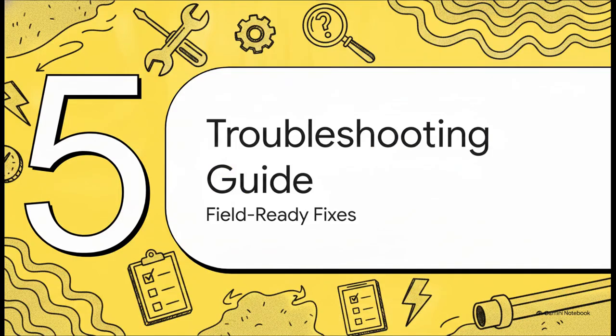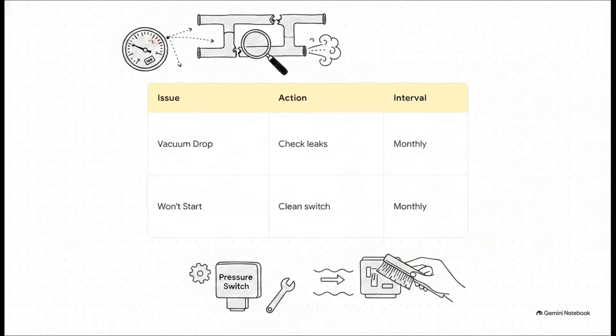All right, Section 5, Troubleshooting Guide, Field-Ready Fixes. Look, even with perfect maintenance, things happen in the field. If you notice your vacuum gauge is steadily dropping, your absolute first move should be consulting the piping diagram to hunt down air leakages. If the system control is spotty or it's failing to engage at the right fluid levels, jump right in and inspect and clean your level and pressure switches. Readjusting those switches is a standard monthly maintenance task for a very good reason. They are almost always the culprit when things get weird.